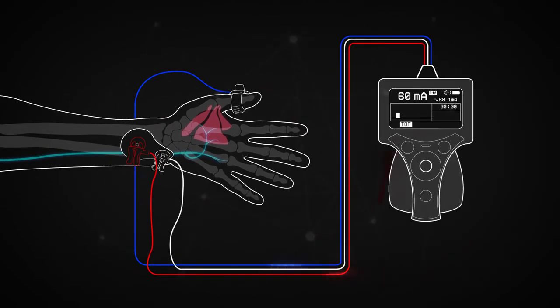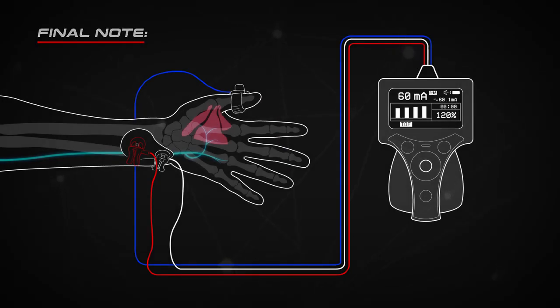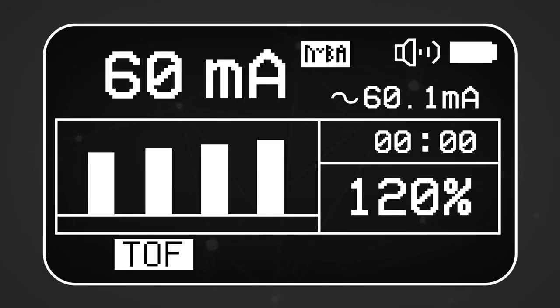Once the setup is complete, a Train-of-Four test can be done in order to observe the patient's muscle contractions. The TOF ratio should be well above 100%. Please note, it's important to verify that the current setting is roughly the same as the current delivered.